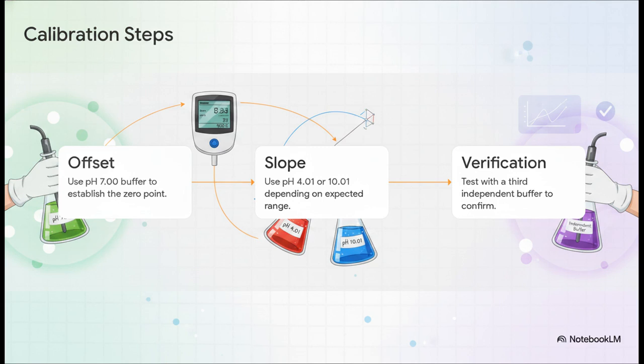Step 1, you must start with the pH 7.00 buffer. This establishes the offset, or the asymmetry potential 0 point. It essentially aligns the meter. Only after that do you move to step 2, the slope, where you use a pH 4.01 or 10.01 buffer, depending entirely on what range you expect your sample to be in. And finally, step 3 is verification. Use a third independent buffer to make sure the mathematical line drawn by your meter actually maps to reality.